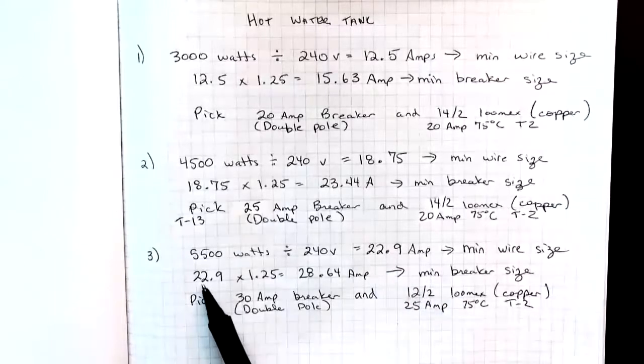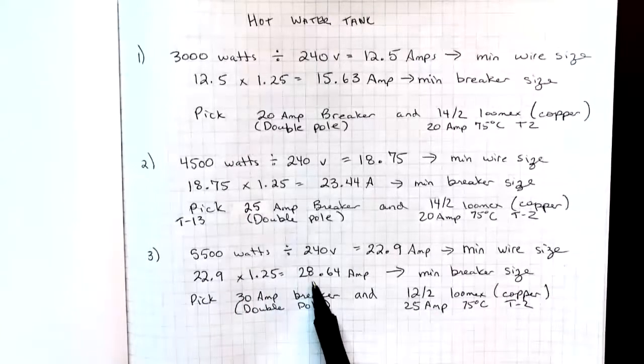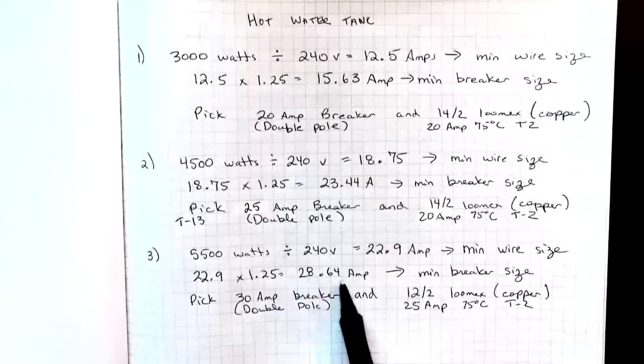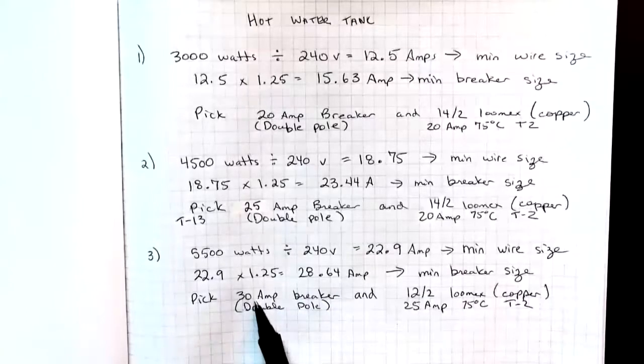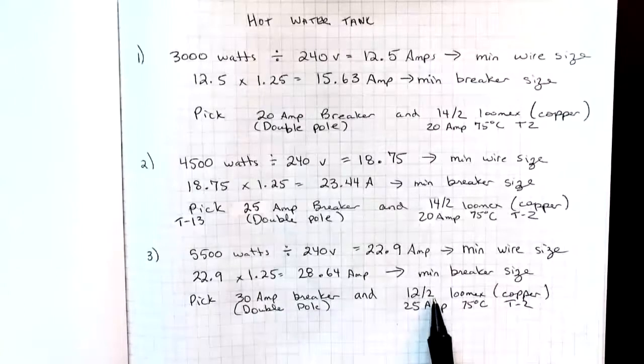And then I take that 22.9 times 1.25 gives me a minimum ampacity for the breaker of 28.64. So I'm going to pick a 30 amp breaker and a 12/2 wire.